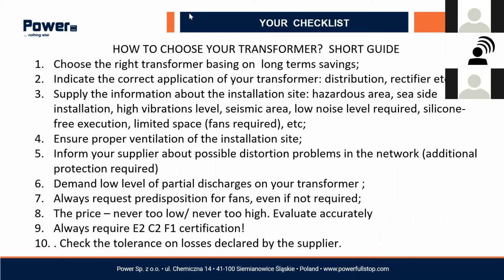Why do I underline this point? This is really a very important point. As a manufacturer, I'm not obliged to put the real values of this parameter for your transformer, but at our company, we do it. We always put this value because the client must know exactly what the partial discharges of the transformer are. And I'm very proud of it because our average value goes from 3 picocoulomb up to a maximum of 6. In some rare cases, we have 7 picocoulomb. So we are much lower than what the rules prescribe. It means the quality of our windings is good, and it means there are not many weak points on the windings in case of a short circuit problem or any other problem in the net.